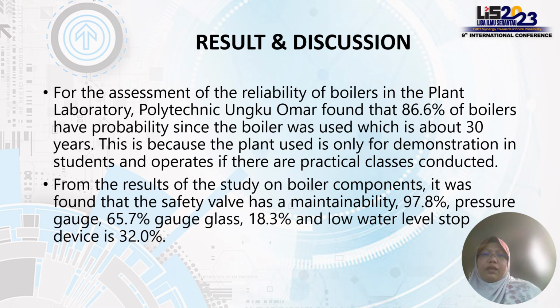For the summary of the result and discussion, for the assessment of the reliability of the boiler in the power plant laboratory of the polytechnic, it was found that 86.6% of the boiler has probability, since the boiler was used for about 30 years. This is because the plant is used only for demonstration in the system and is operated when particular classes are conducted. From the result of the study on the boiler components, it was found that the safety valve has a maintainability of 97.8%, pressure gauge 65.7%, gauge glass 18.3%, and low water level is 32%.